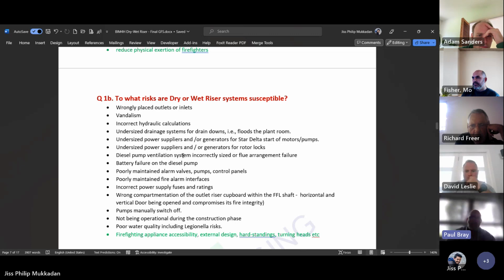But the dry riser drain down valve is in the inlet delivery, which is on the outside of the building. So you can either connect it to a hose, which I very rarely see done, or you just open up the drain valve and it will drain itself and empty itself out, which is good practice after use because it reduces the risk of corrosion. So that's a risk for wet risers, but not dry risers. Well, is that what we're saying?